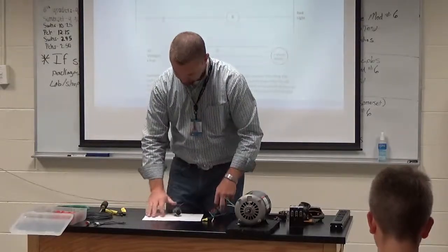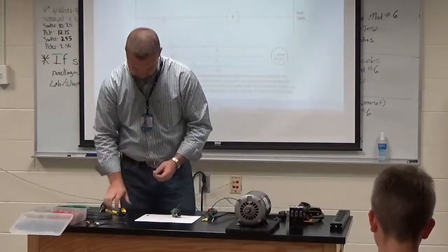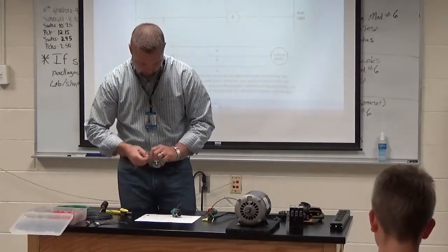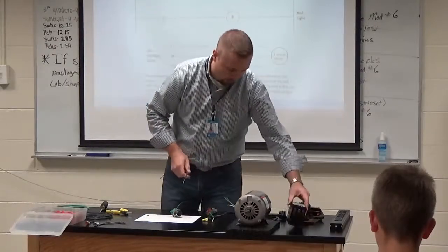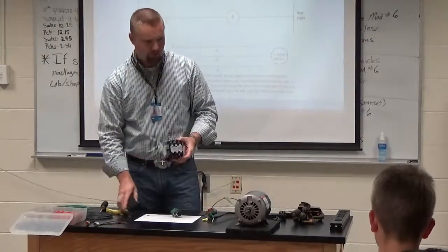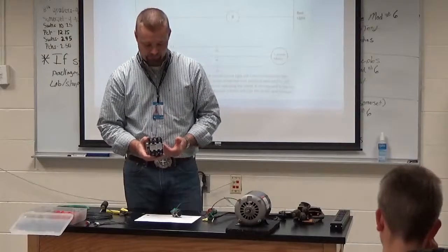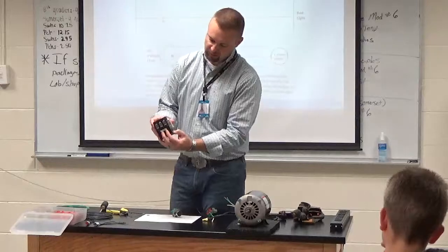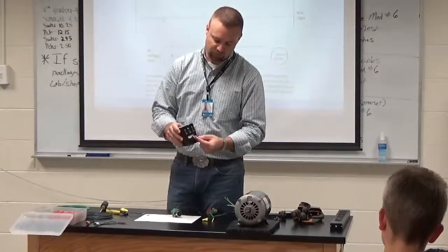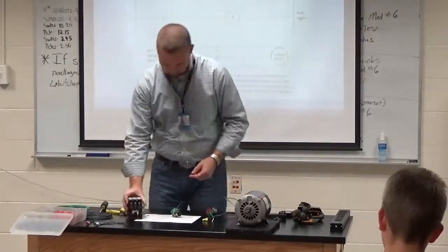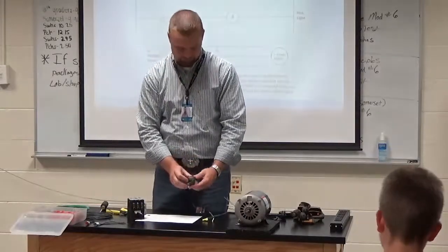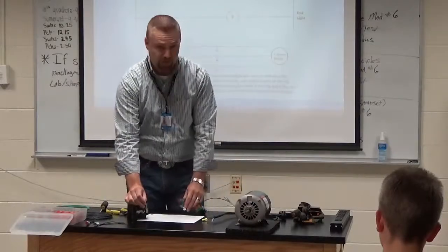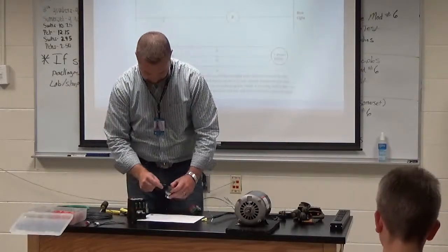Now it must go where, guys? Look on your schematics, as we're following through this, where does it go out of my stop button? To the other side. Yes, to the motor starter on the coil, right? So the particular motor starter I'm using is two top, yes. Two top. So this is my coil, as you guys see here, on my starter. Basically got an input and an output on my coil. So I'm gonna run the wire from my start button on the normally open side over to one side of my coil. That's my very next step.